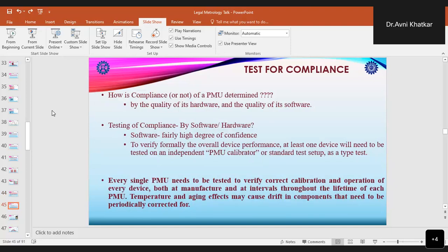Now, when we talk about the test for compliance, whether the PMU is compliant or not will be determined by the quality of its hardware and the quality of its software. The PMU software can largely be designed using mathematical tools, and it can be tested in simulation in conjunction with knowledge of the PMU hardware constraints, giving a higher degree of confidence that the PMU will behave appropriately. These activities can be carried out at the manufacturer premises. However, in order to verify formally that the overall device performance, at least of a single device, is appropriate, these activities should be carried out in a formal environment at an independent PMU calibrator or a standard test setup as a type test.